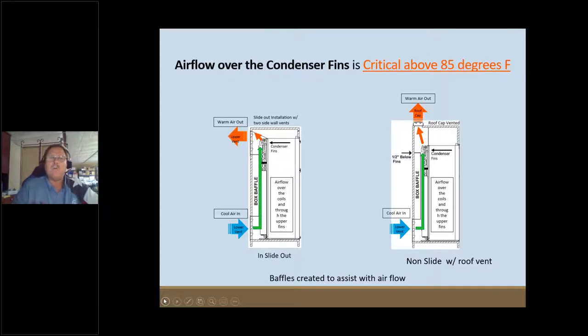If you're somewhere with temperatures of 90 to 95 degrees and you have poor airflow across the coils, the ambient temperature rise will also raise the temperature inside the box because the box isn't getting rid of its heat — the gas becomes saturated and says, 'I can't take anymore.' So take that bottom louver vent off and check: no more than a half inch between the refrigerator and that back wall. Poor airflow is like having a Walmart shopping bag on the front grill of your truck — your engine gets hot because there's no airflow to move the heat.